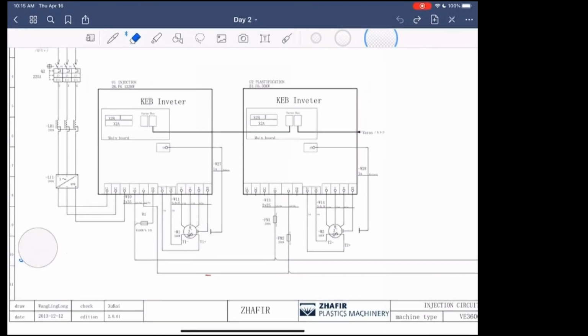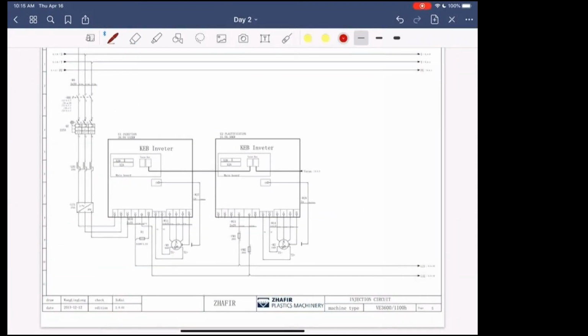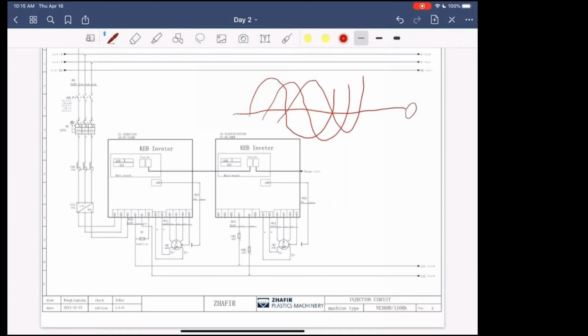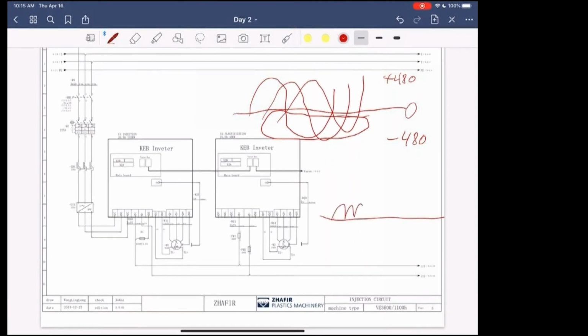This squiggly line down here, I'm going to explain in a minute. So what happens with an inverter? What an inverter really does is it takes an AC signal. An AC signal is 60 hertz. It goes like this, three phase, so it's going to be three of them. And you have 0 volts here, a plus 480 volts here, and a minus 480 volts here. So what an inverter does, it takes this signal over here, the negatives, and inverts them. So what you have is all positive values for your signal.